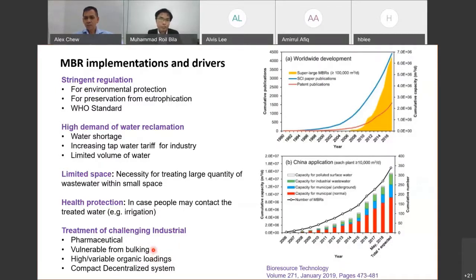Another driver is that some wastewaters have a tendency to disintegrate the sludge. So basically, the microorganisms cannot form a very good floc. For example, phenolic wastewater is very hard to treat biologically. And then some industries, like food processing industries, have variable loadings. For example, in the morning, they produce a lot of wastewater with very high concentration of COD, while later in the evening, basically there is no production, there is no activity. So at that time, they don't even have wastewater. So that's also a problem if we use the conventional process.